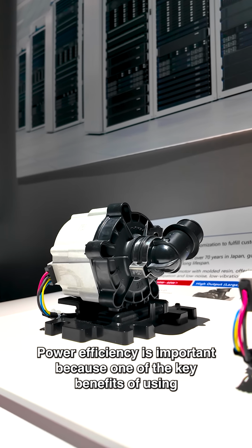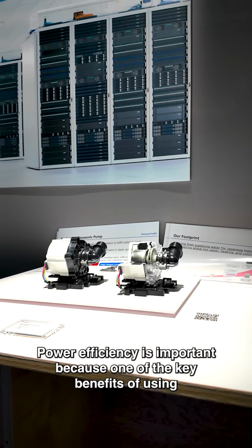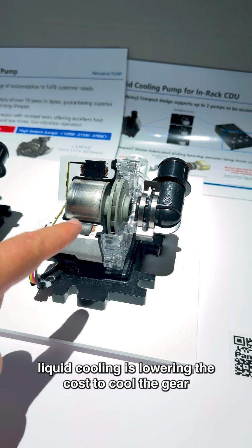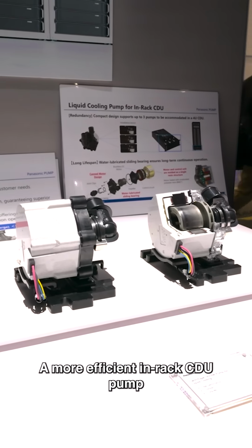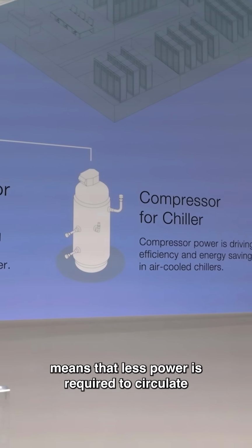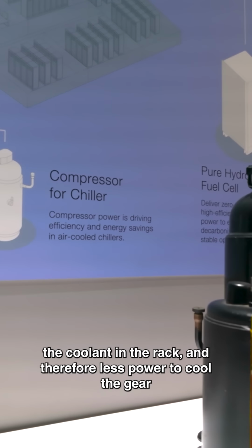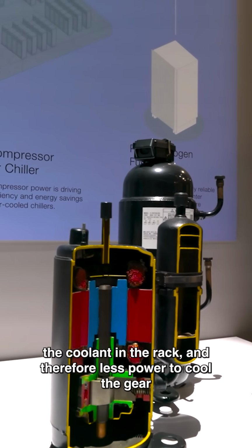Power efficiency is also important because one of the key benefits of using liquid cooling is lowering the cost to cool the gear. A more efficient in-rack CDU pump means less power is required to circulate that coolant in a rack, and therefore less power goes to cool the gear.